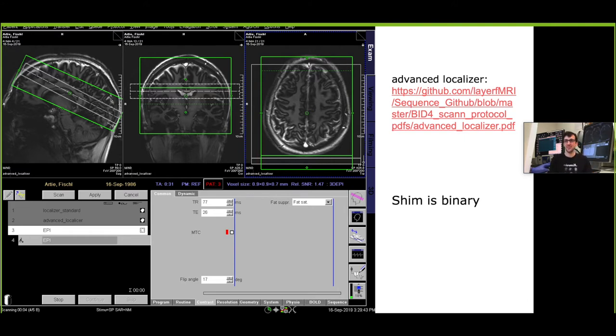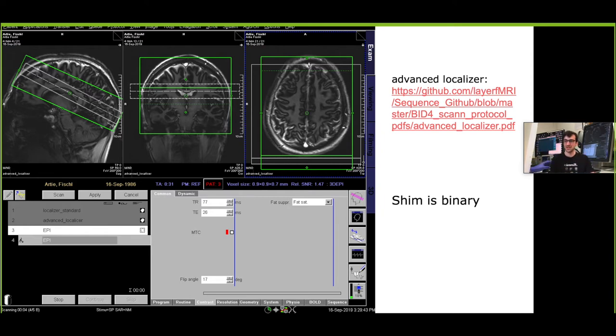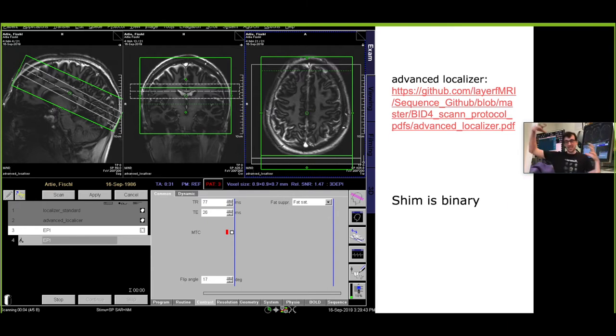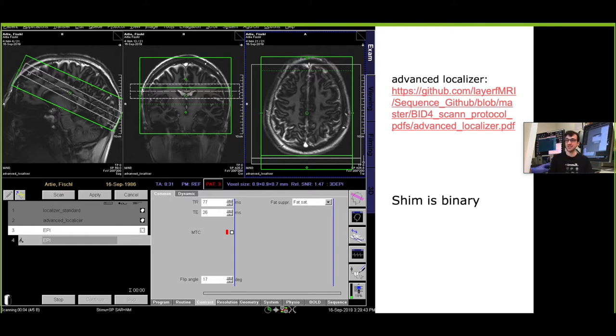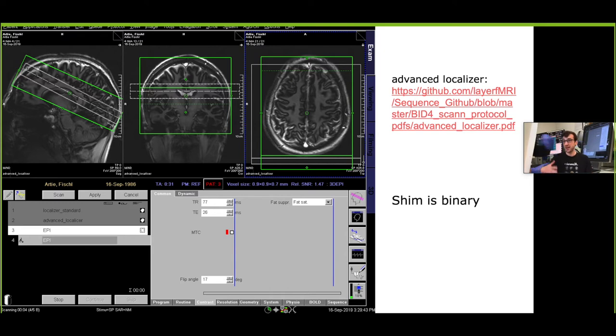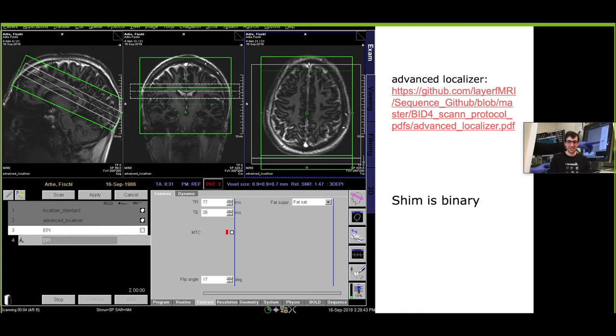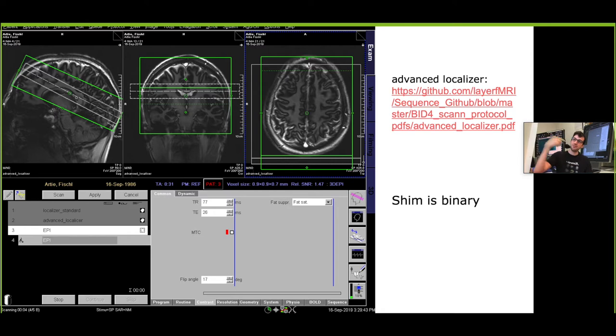Additionally, I usually don't restrict it to the part of the slice that I care about, namely here the calcarine sulcus, but in fact I make it so big that it covers the entire field of view even though we need to make some compromises here. Note that the Nyquist ghost correction is done in k-space in the center of k-space, so literally it takes the average of the entire slice. Even though we want to optimize this part only, if the shim would be very bad up there the Nyquist ghost correction which corrects partly for spatially specific eddy currents would be very bad and therefore we would have fold over that compromises our signal.